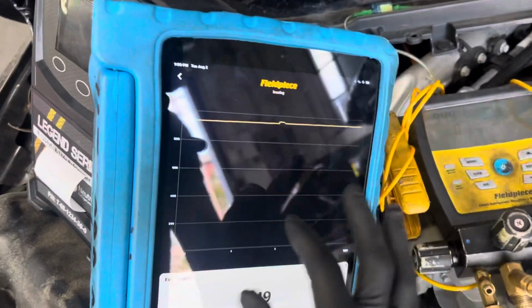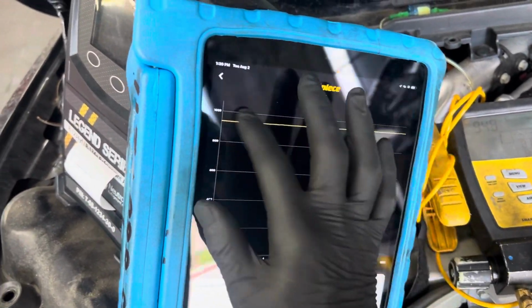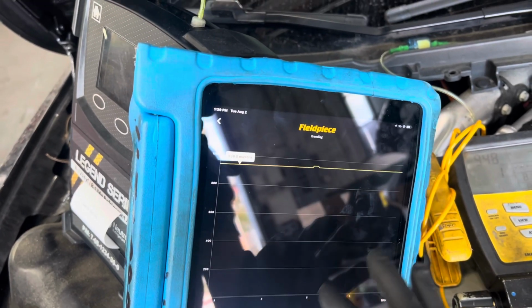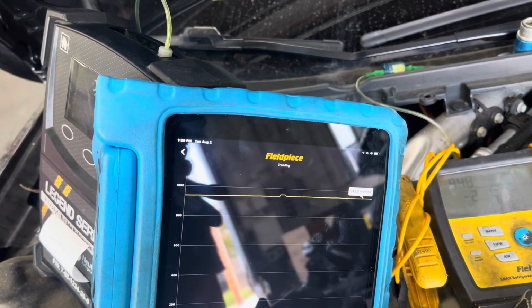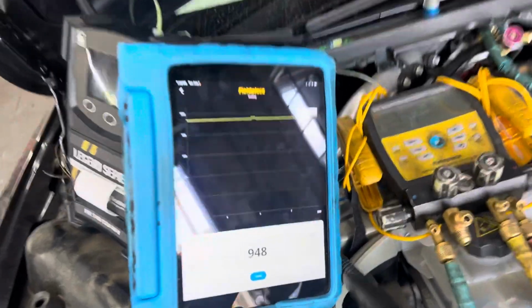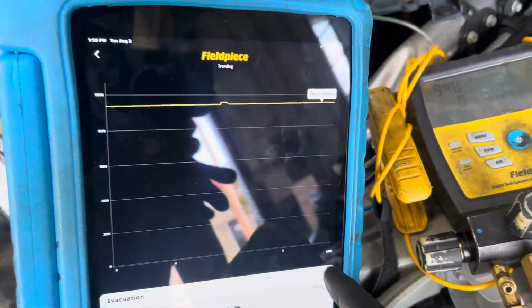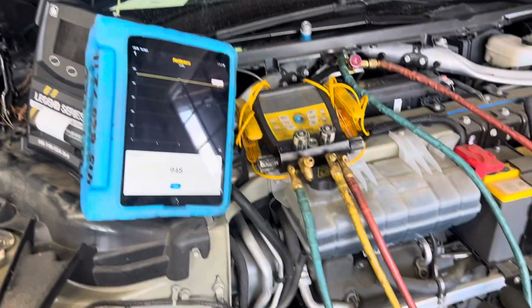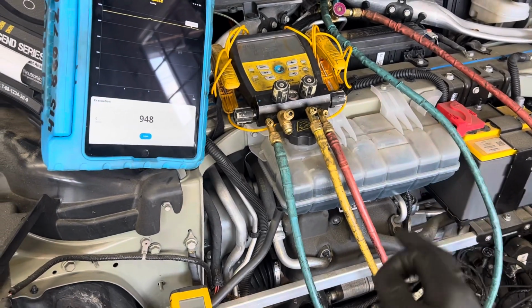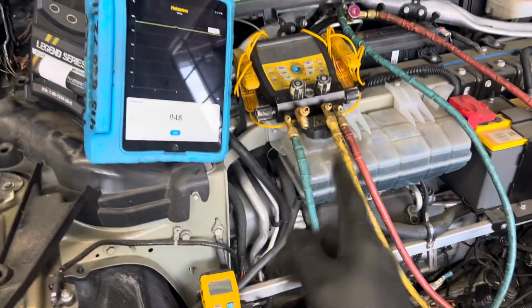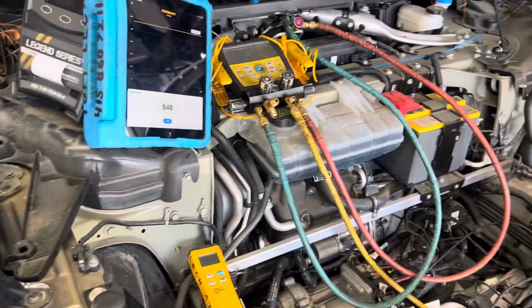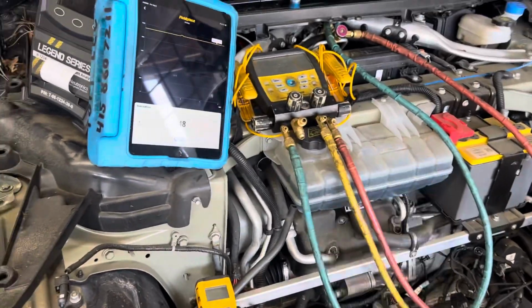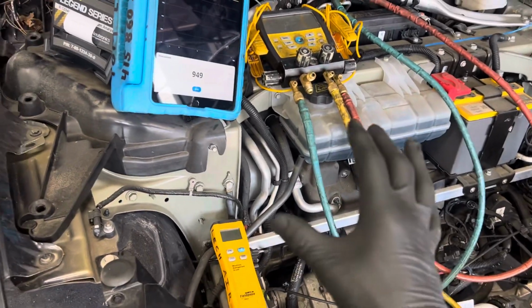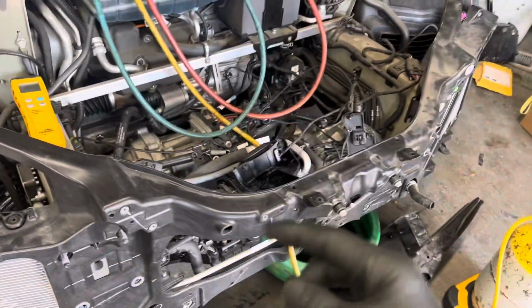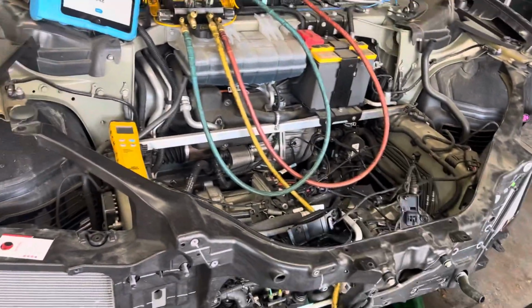And so we started out, let's see, where do we start out? 938 microns, and we're at 949 microns, and we're going up to minute number 7. So I'm thoroughly satisfied that the system is completely drained of refrigerant. This is YF refrigerant, so at $207 a pound, you want to get every ounce you can and not waste it. But now here comes the difference between a hack shop and a real shop.